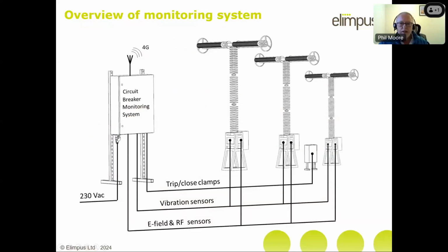This gives you an overview of the way the monitoring system operates. I'm showing this on an air-insulated circuit breaker, but it has been equally applied to GIS. It's just a slightly different application. So we have a monitoring box with all the recording hardware in it. We then record the trip and close signals. Normally you get that from a little monitoring kiosk which is close to the breaker.